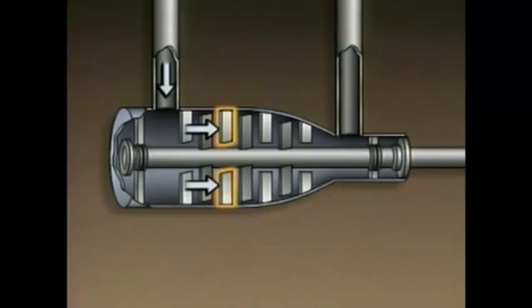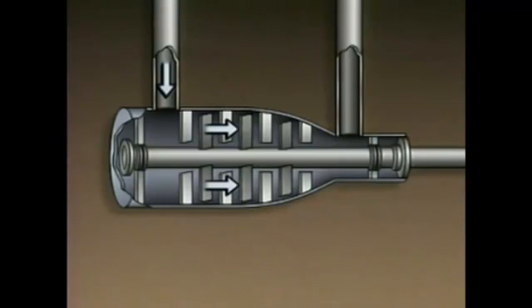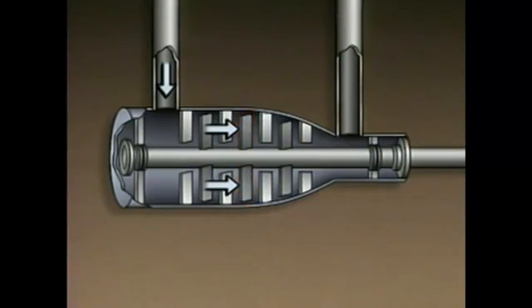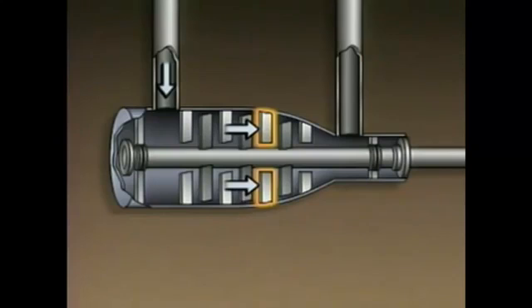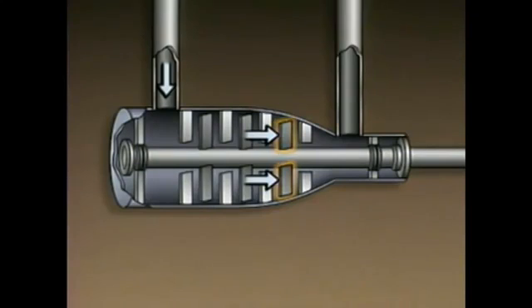In some cases, the stationary blades can also be opened and closed to help control gas flow. As the gas passes by the stationary blades, it slows down, which increases its pressure. After passing the stationary blades, the gas contacts the second set of rotating blades, where its velocity is increased again. From these rotating blades, the gas moves by another set of stationary blades, where the gas slows down again, increasing its pressure even more. The gas is then directed toward the next set of rotating blades. This process continues as the gas moves through the compressor and then out through the discharge line.